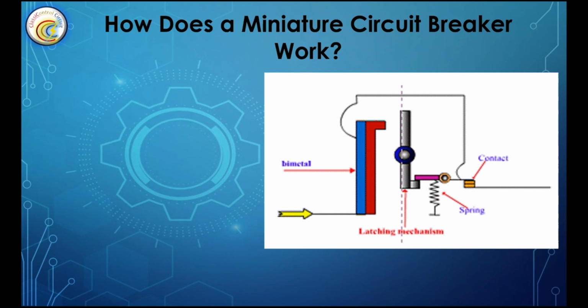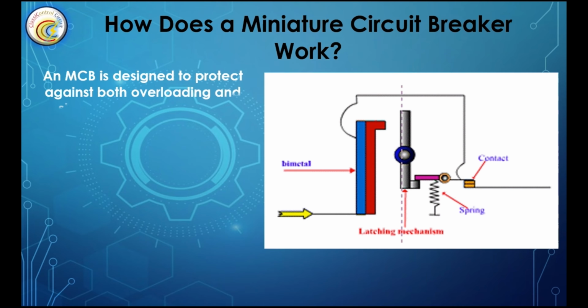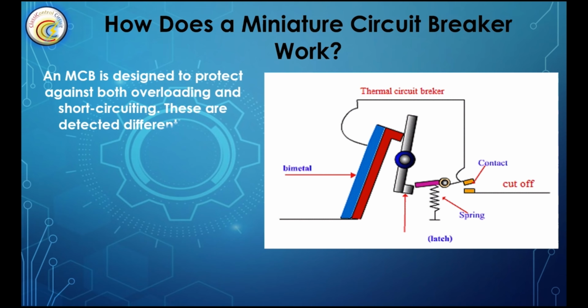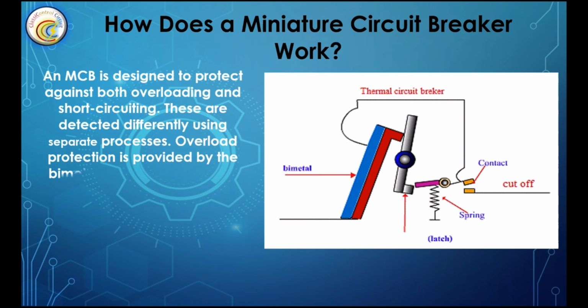How a miniature circuit breaker works. An MCB is designed to protect against both overloading and short-circuiting. These are detected differently using separate processes. Overload protection is provided by the bimetallic strip using thermal operation, whereas short-circuit protection is provided by the tripping coil via electromagnetic operation.